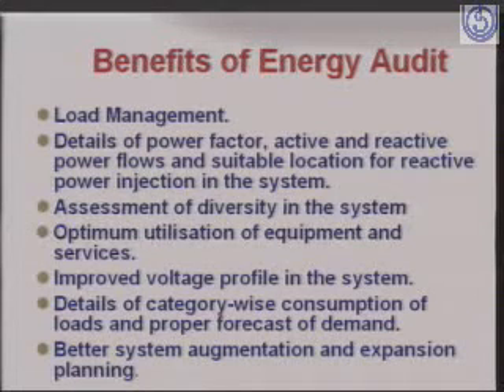So through this energy audit, we will be in a position to find out the locations where a lot of reactive power is coming on the system. Accordingly, we can decide the location, and we can install the power factor capacitors. You know that power factor capacitors improve the power factor from the point of its location to the generating site. For example, if we have a power factor capacitor installation on the primary side of a transformer, it will not affect the power factor on the secondary side of the transformer, because from the primary side it is going to reduce the lagging reactive power from that point of installation back to the generating side, that is to the power station side. So from energy audit, we will be in a position to find out the exact locations of such installation.